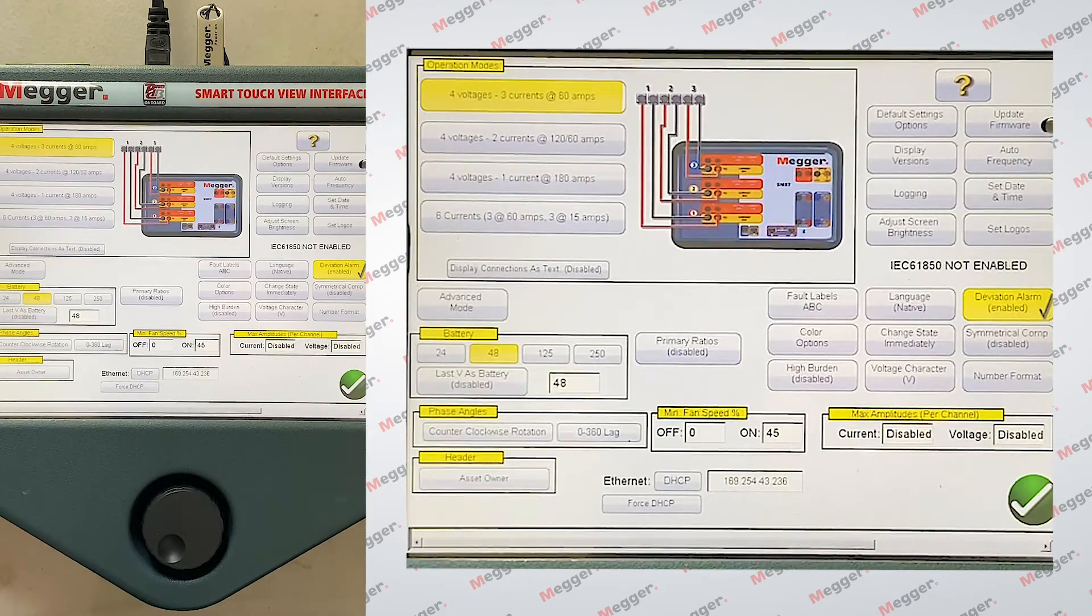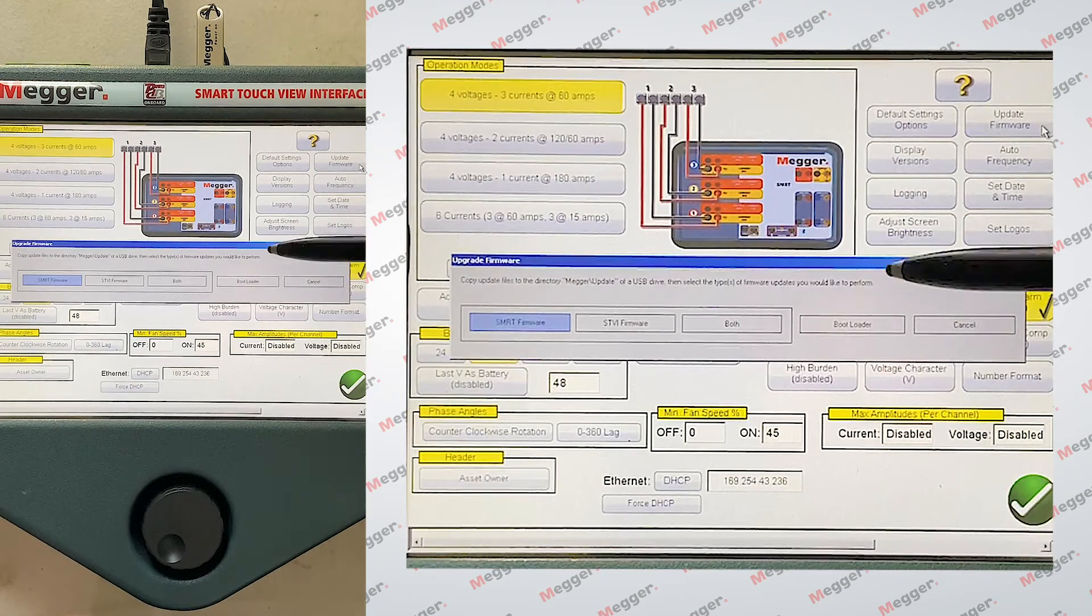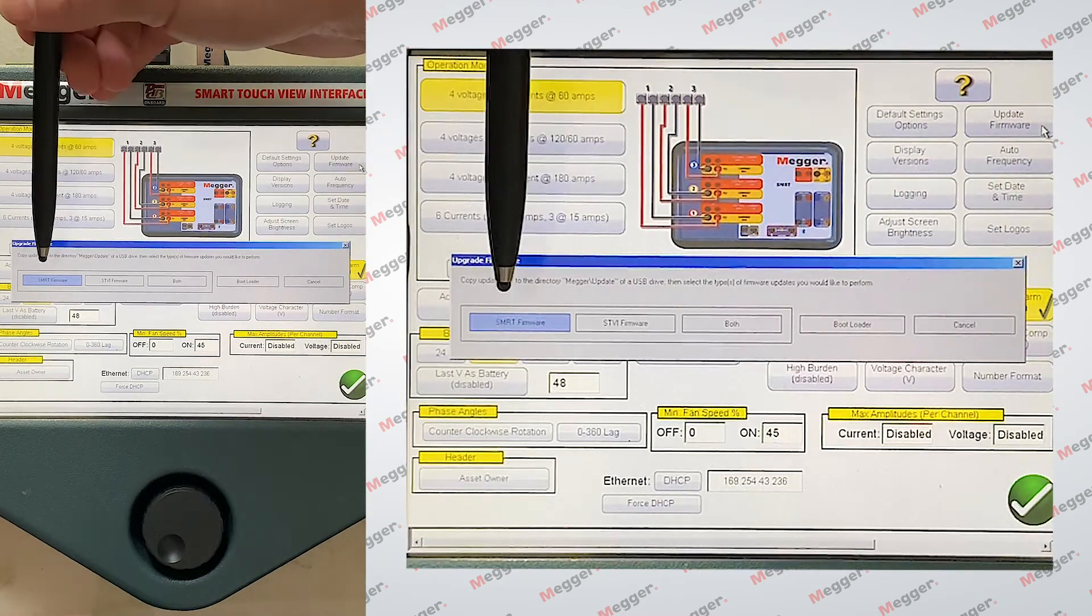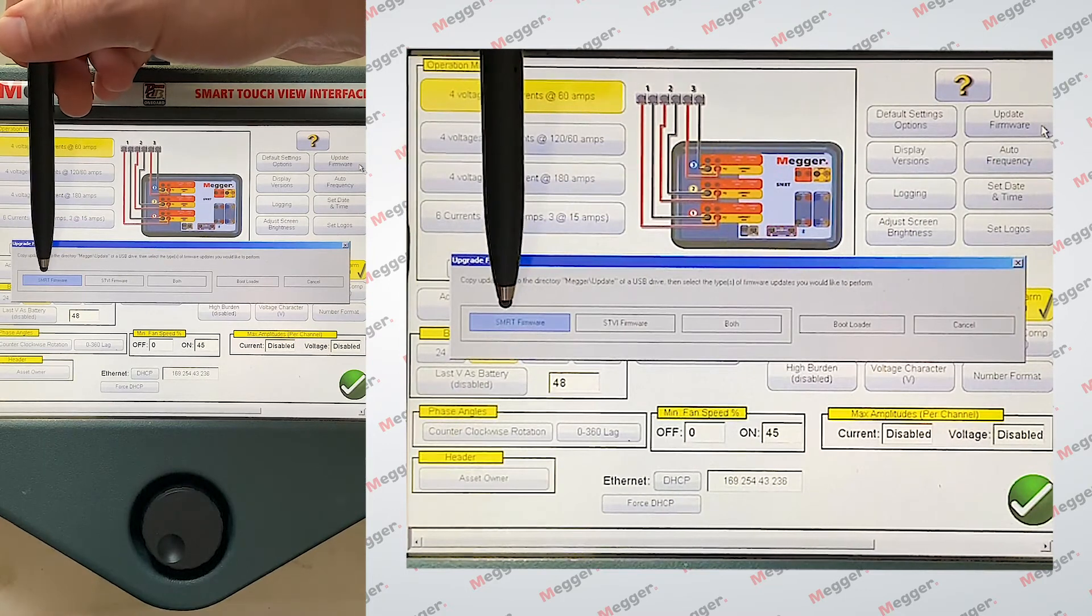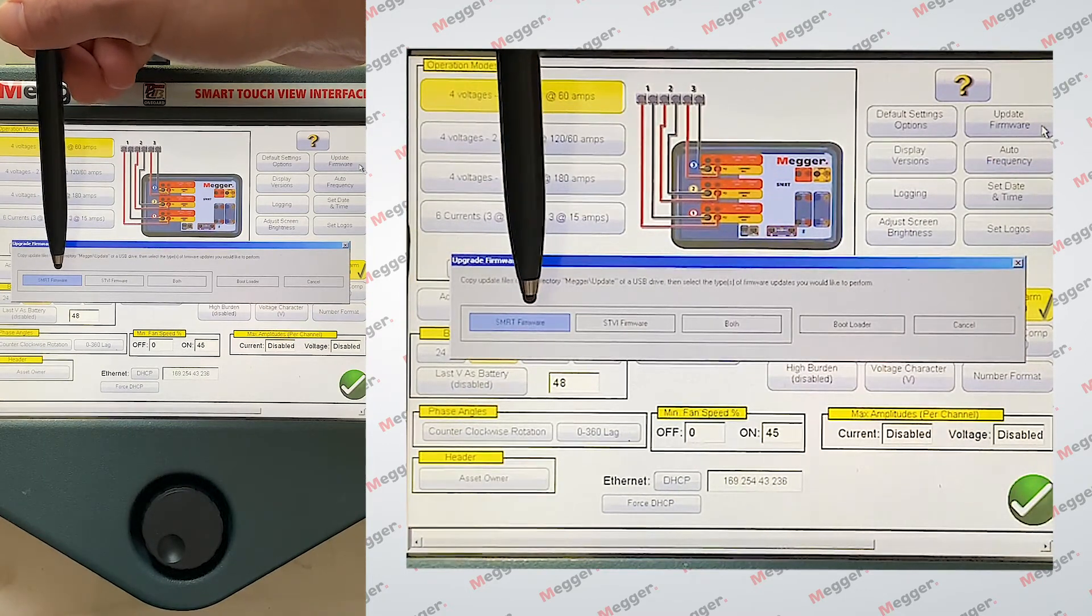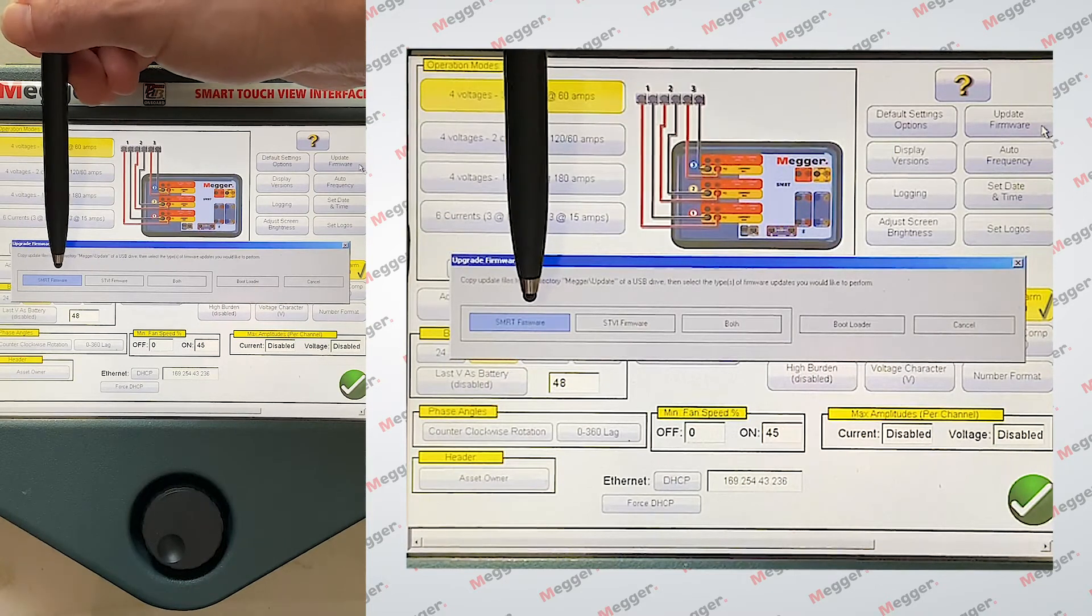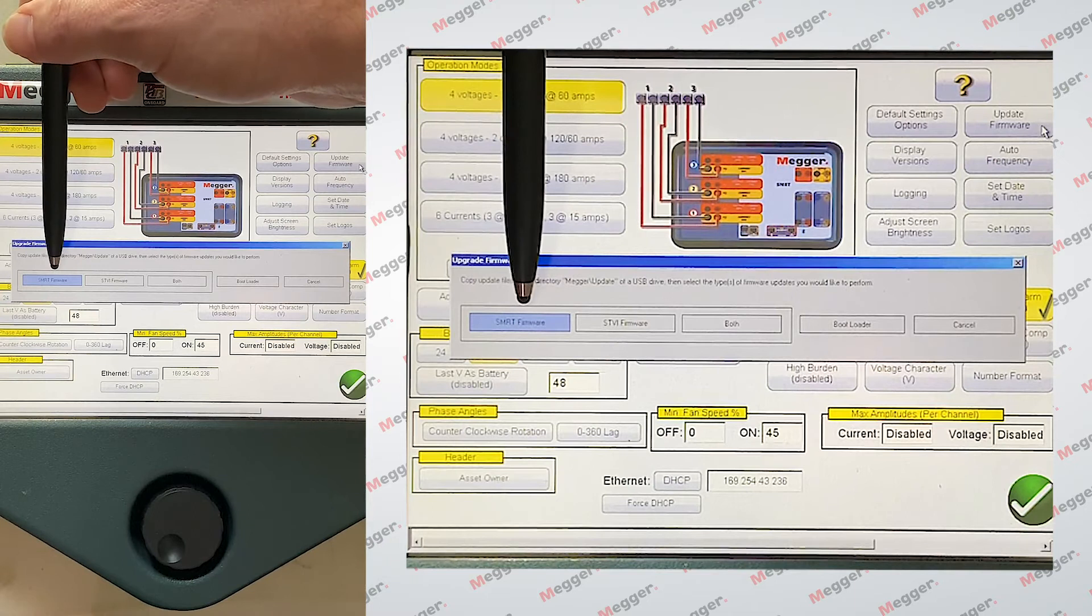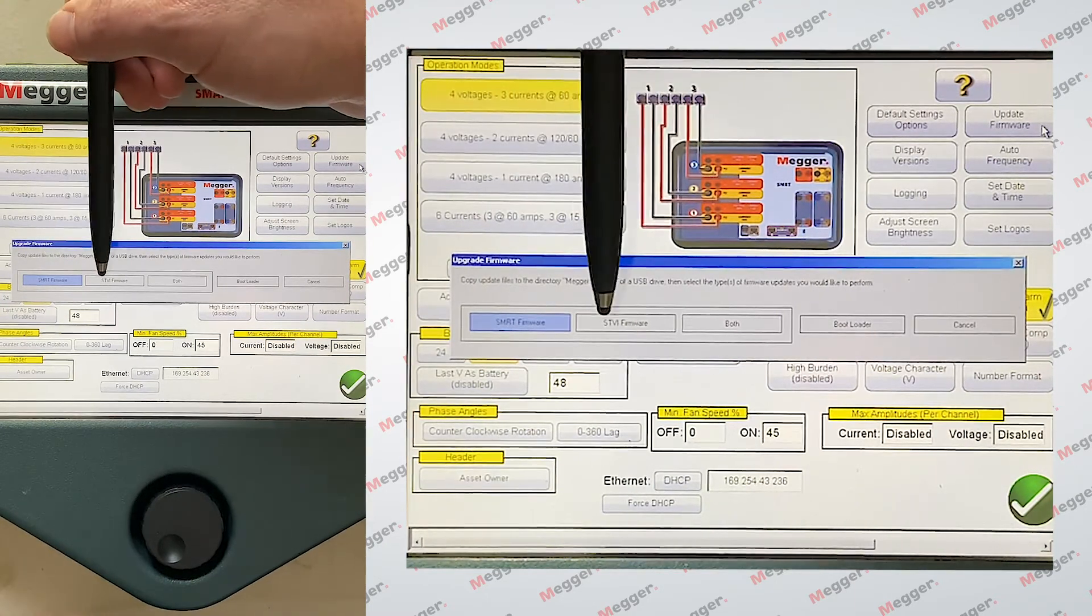I want to go to update firmware. So this is the pop-up window I was talking about. And it gives us a couple of options here. It gives us update the SMRT firmware, which as I was saying earlier, the firmware version of each generator will get updated to the latest firmware release that you currently have placed on your thumb drive.